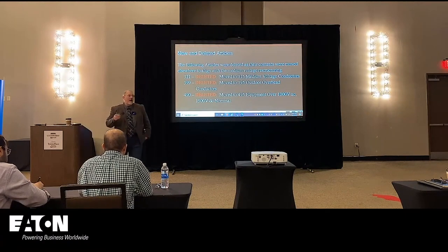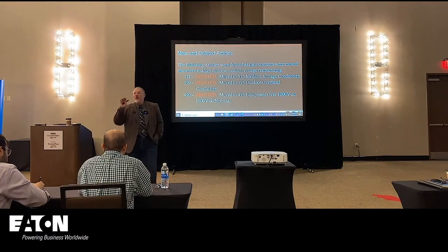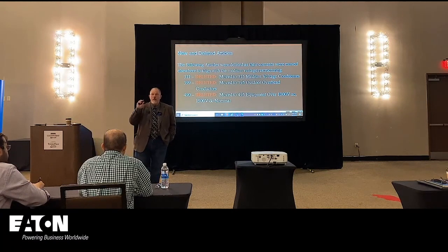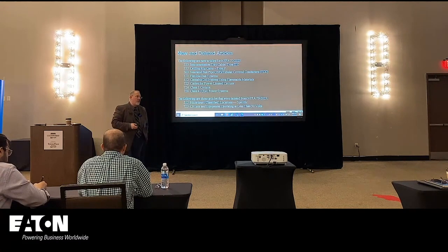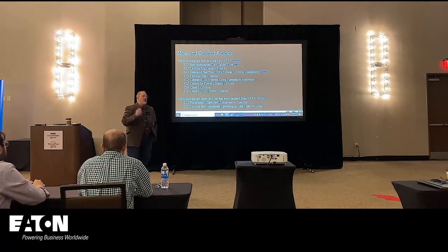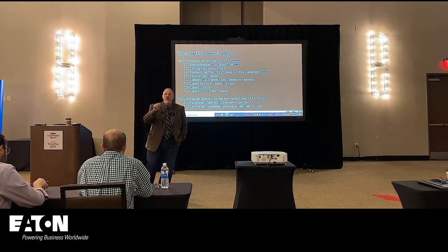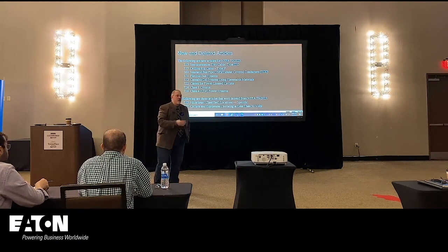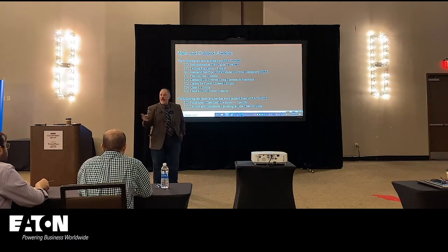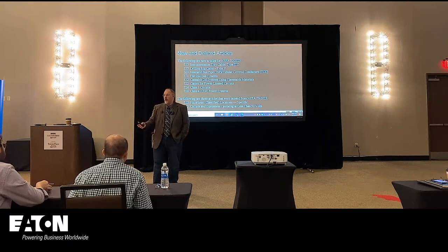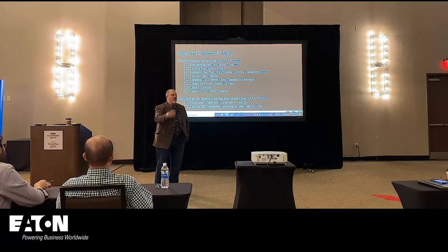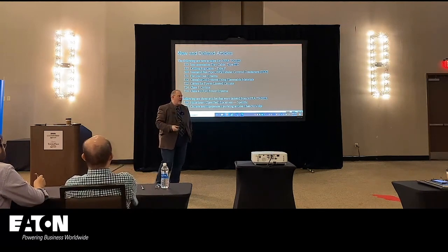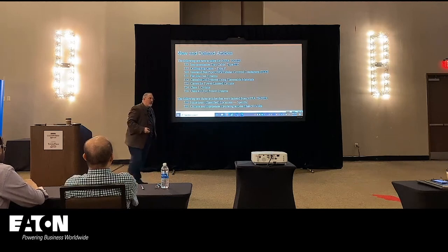And again, if I would hazard a guess, the technical changes in those articles are minimal, if any, because the primary focus was to just line up the medium voltage articles in the code. So it's getting some love. For medium voltage applications, we're recognizing there are some technical issues with the requirements. Medium voltage equipment, you don't do 1.25 times the load. It's not 80% rated equipment. It's 100% rated equipment. Yet the NEC sort of implied that it was 80%. So we're trying to add that clarity in the code.